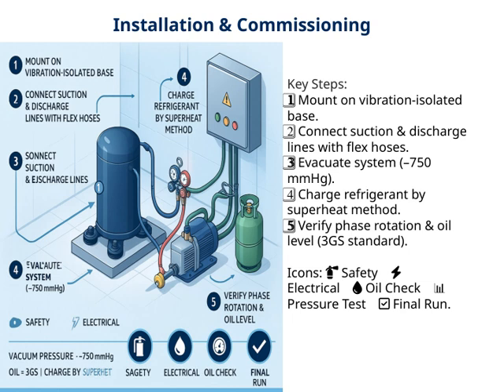Once the system is evacuated, we charge the refrigerant using the superheat method. This approach helps us ensure the right amount of refrigerant is added, optimizing efficiency. Then, it's important to verify the phase rotation to make sure the compressor runs correctly, and check the oil level according to the 3GS standard. Proper oil level is vital for the compressor's health and smooth operation. Throughout this process, safety is paramount, so always keep safety icons in mind, like for safety precautions, high voltage for electrical connections, droplet for oil checks, bar chart for pressure testing, and white heavy checkmark for the final run. Following these steps thoroughly will help ensure a successful installation and reliable operation of the system.